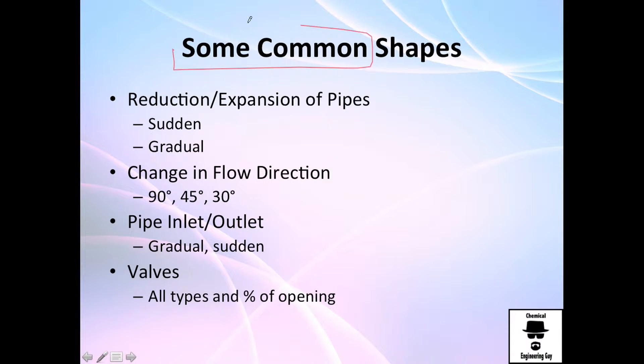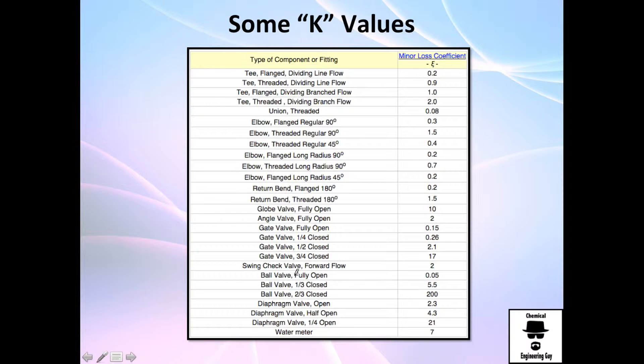There are many common shapes we have in the market. For example, reduction and expansion of pipes is very common. It's very easy to find them. Change in flow direction, which is also elbows we have. We have even return 180 degree, which is this elbow right here. Pipe inlet and outlet is very useful, especially if you have a tank. There's a friction loss when it goes through this here, and there's a friction loss as well when you deliver to the tank. And more importantly, we have K values for valves. We need K values for valves and for its percentage of openness. It's open to 50% is going to be different than that of the 20%. So let me show you many K values from internet, databases, books, and so on.